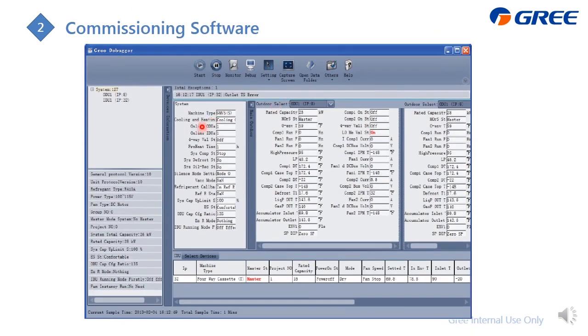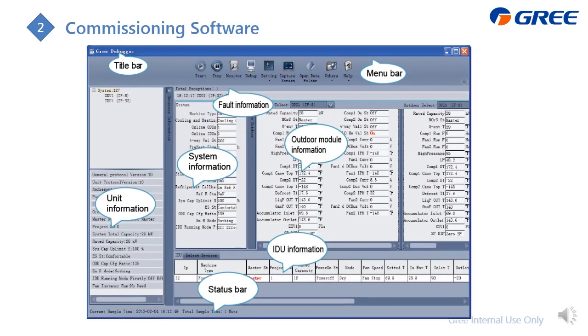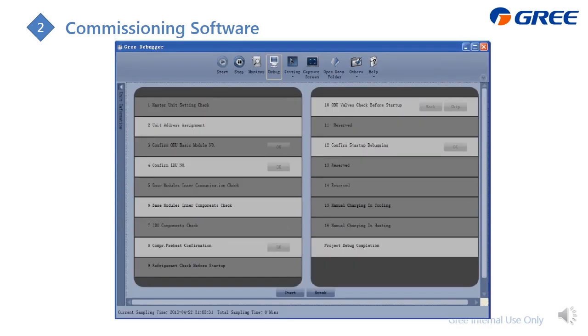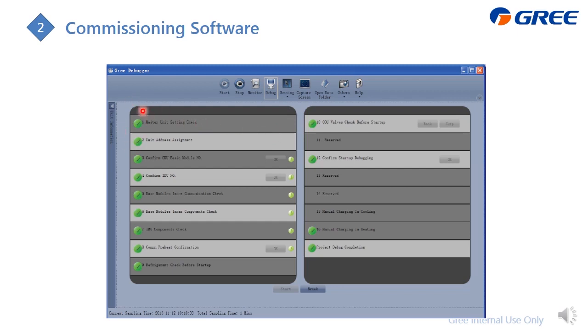So from here you can see all the parameters of the outdoor unit, indoor unit, and also the system information, this part and this part. As for the commissioning, just add here, this is the bar, and all the steps we will display directly to you. And also, if it is okay, it will display this green mark. If it is not okay or an error, it will also display the error code directly to you.